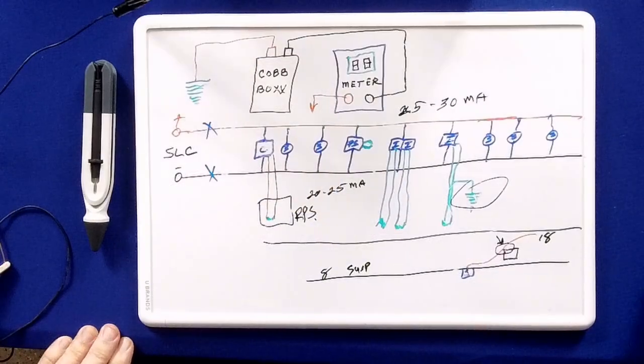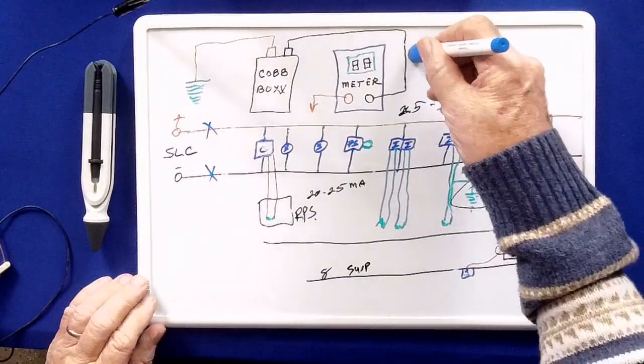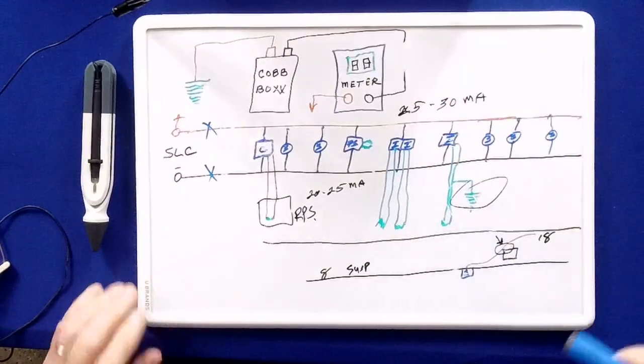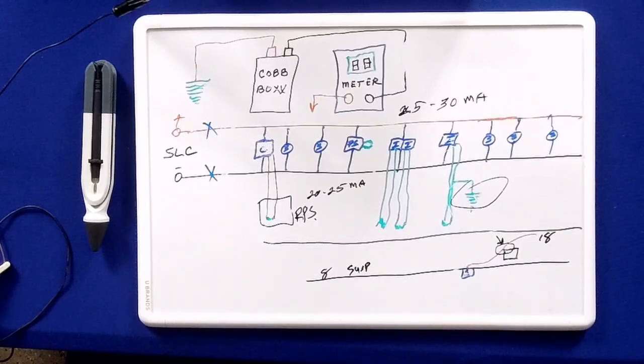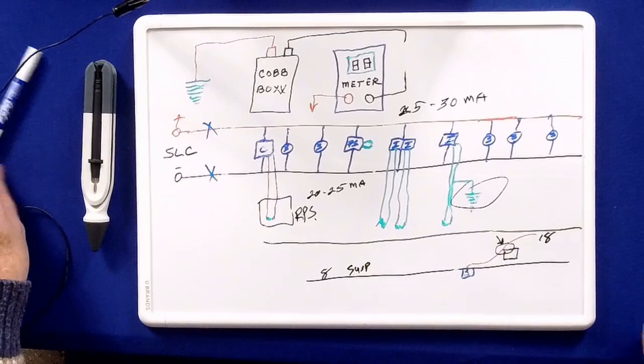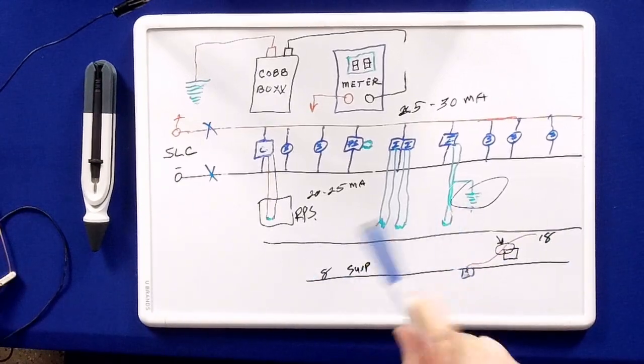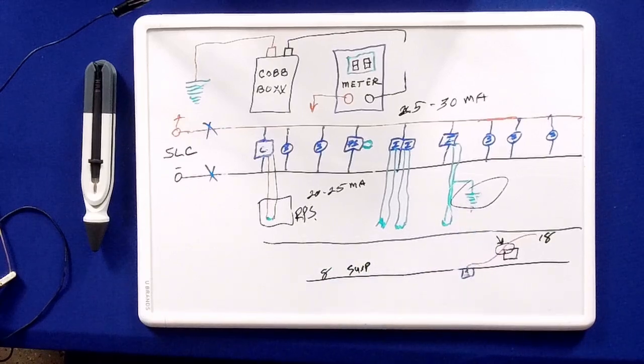Now, let me tell you about the time that I found a ground fault in a 50,000 seat stadium in about an hour and 15 minutes. And the way I did that, I'm going to show you here real quick, is I was reading current as I normally use. And what I was seeing was it was just floating all over the place, just going nuts. Now, you can see it a lot better with an analog meter that's got the needle on it rather than the digital meter. But here's a way around that.